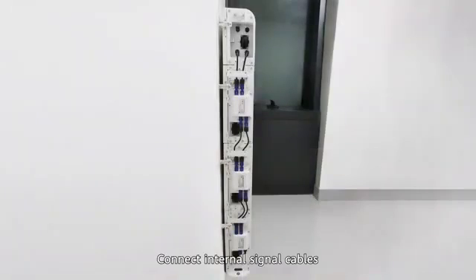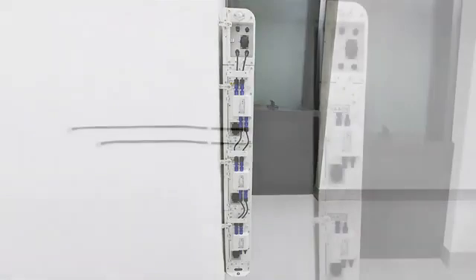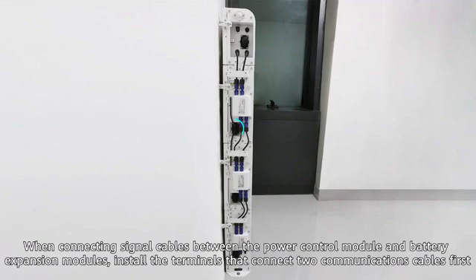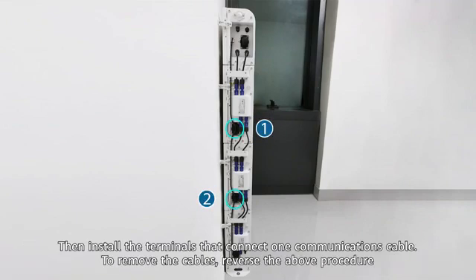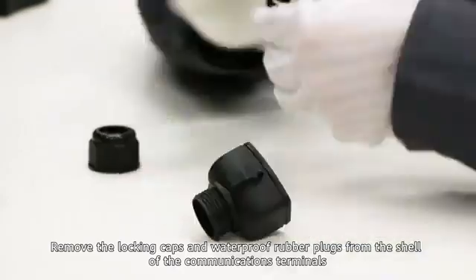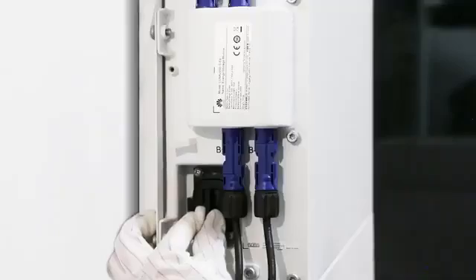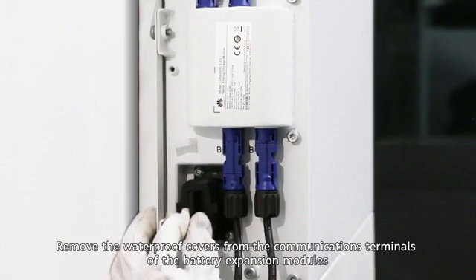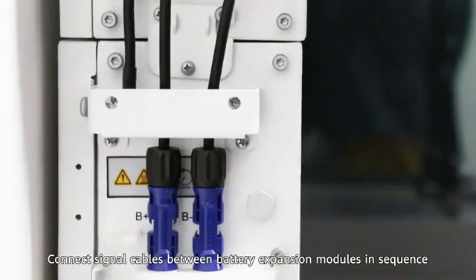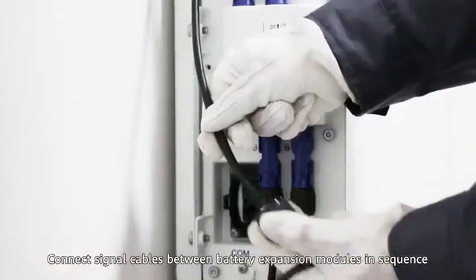Insert the internal signal cables. When connecting signal cables between the power control module and battery expansion modules, install the terminals that connect two communications cables first, then install the terminals that connect one communications cable. To remove the cables, reverse the above procedure. Remove the locking caps and waterproof rubber plugs from the shell of the communications terminals. Remove the waterproof covers from the communications terminals of the battery expansion modules. Connect signal cables between battery expansion modules in sequence.